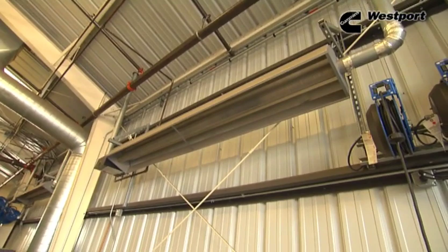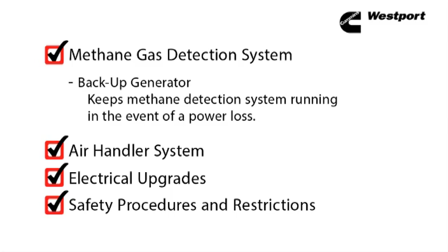First, a methane gas detection system, which will include a backup generator to keep the detection system running in the event of a power loss. Second, an air handling system for proper ventilation, which would involve opening doors and activating ventilation fans. Third, any needed upgrades to the electrical and heating systems. And fourth, making sure all safety procedures and restrictions are observed. We'll take a look at each of these key areas.